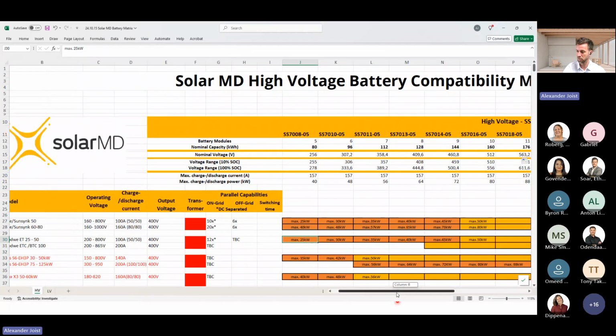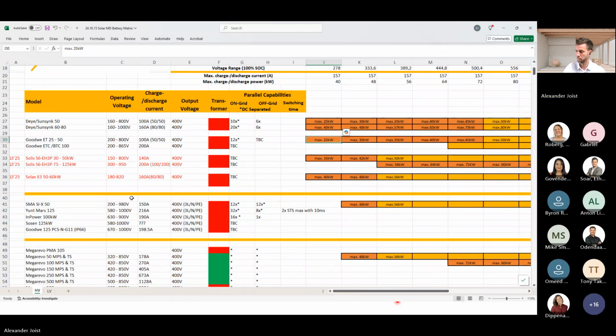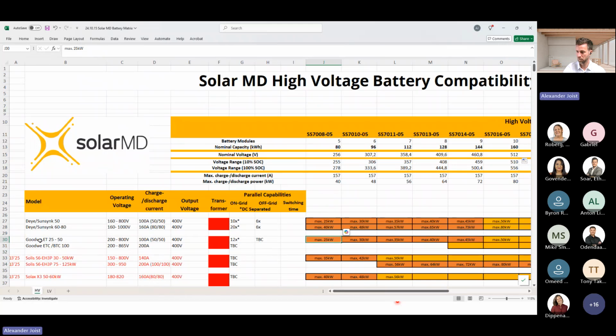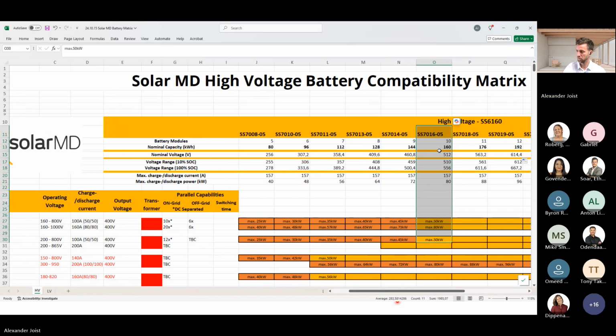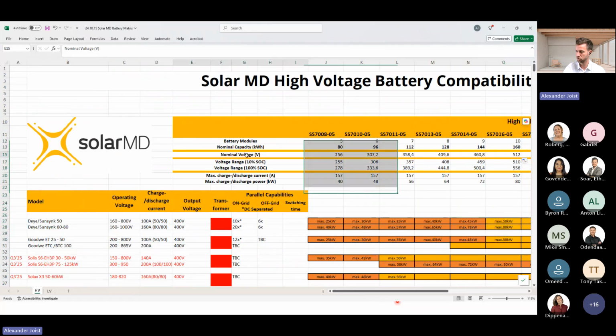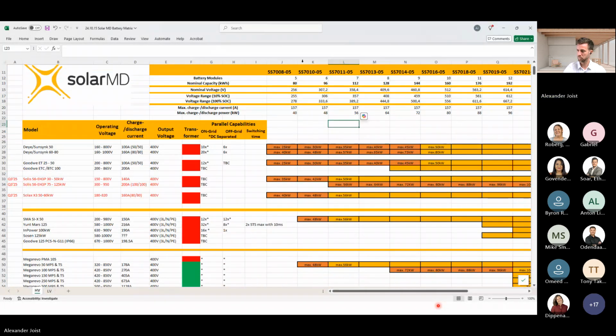So you can see, even though I'm using, let's say, the GoodWe 50, I can only use the full capacity of this inverter at this stage with this battery. So we need to be careful of what we use with high voltage. It's quite important to know the voltage of the battery, the maximum charge and discharge current of the battery, as well as the same information from the inverter. I will send this around so you can use it. It's quite a nice overview that you can then use to size your batteries and see how much energy or charge and discharge current you have got.